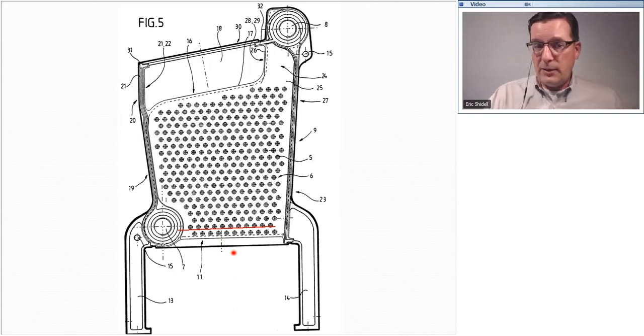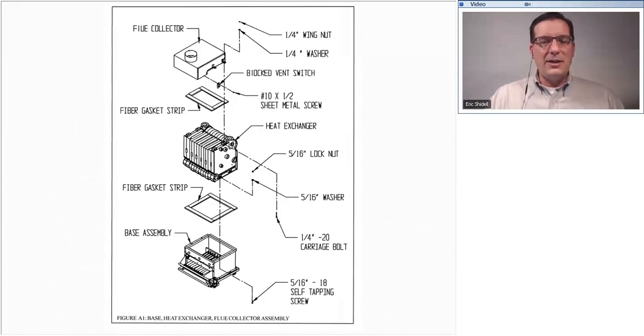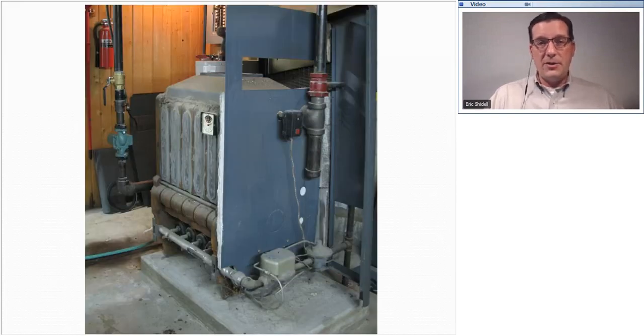And when we do think about a new boiler, there's nothing wrong with going back with a cast iron boiler again, except for the fact that if you're the person who has to haul it down the stairs, you might want to go with a lighter weight option. Here's another example of the cast iron heat exchanger. And this is from a brand new modern era boiler. You see the multiple sections bolted together. They sit upon a base now. Instead of having the legs that sit down, there's a metal base made for the heat exchanger with a gasket in between. Burners down below. A flue collector box bolted to the top. Boy, that is pretty much the same thing as this, isn't it? That's right, which is pretty much the same thing as this.